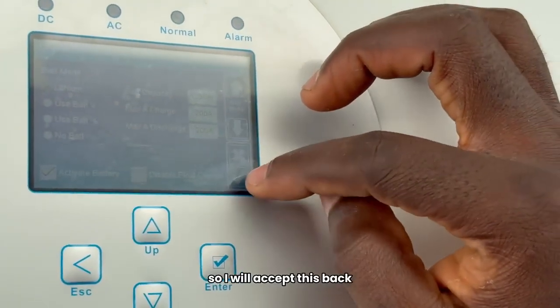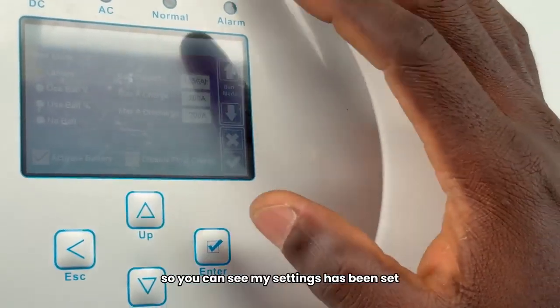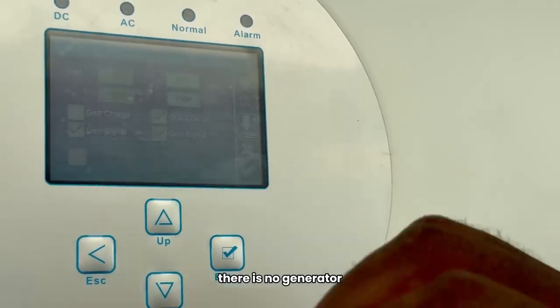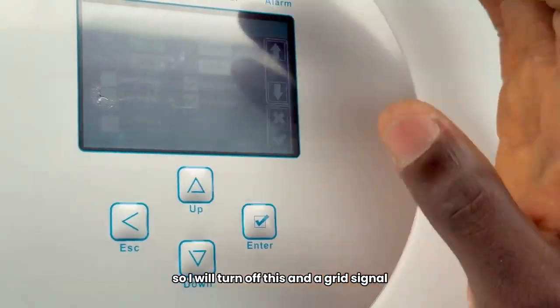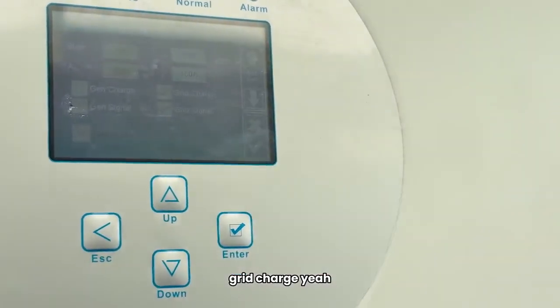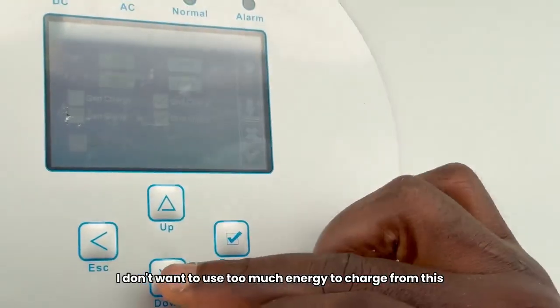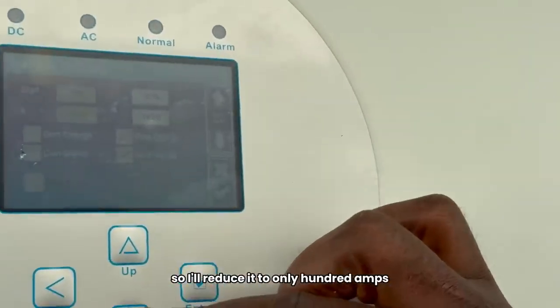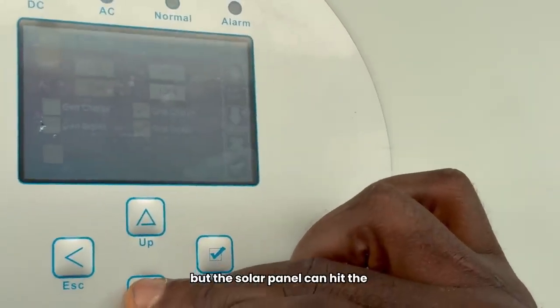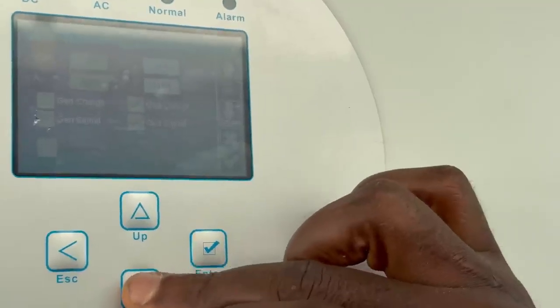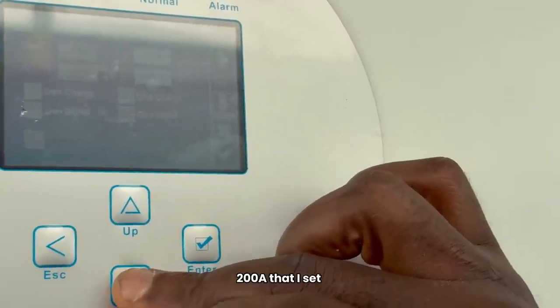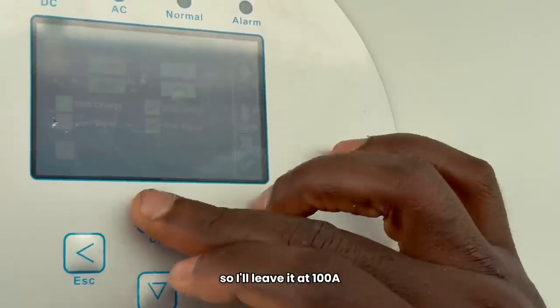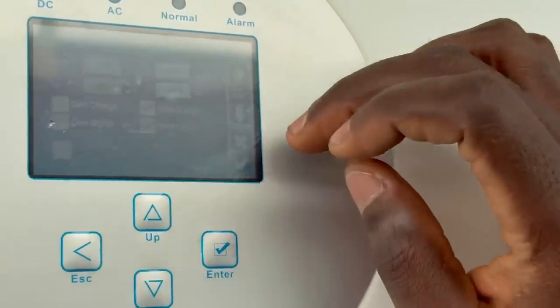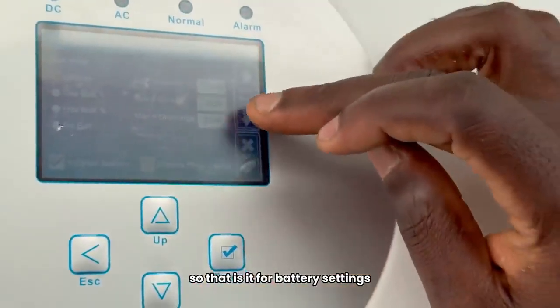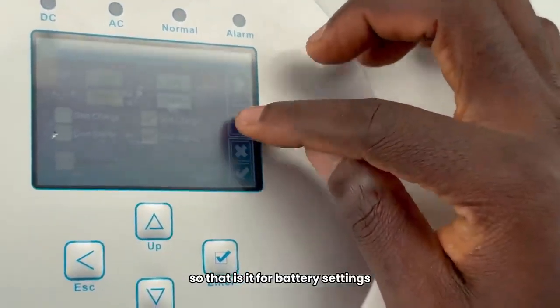Okay, I'll accept this. You can see my settings have been set. There's no generator, so I'll turn off the grid signal and grid charge. I don't want to use too much energy to charge from this, so I'll reduce it to only 100 amps, but the solar panel can hit the 200 amps I set. So I'll leave it at 100 amps. That is it for battery settings.